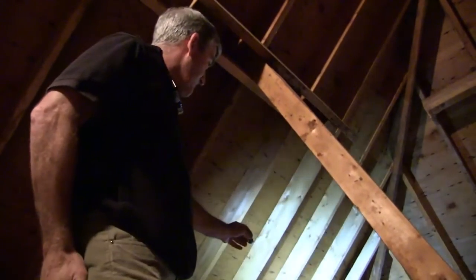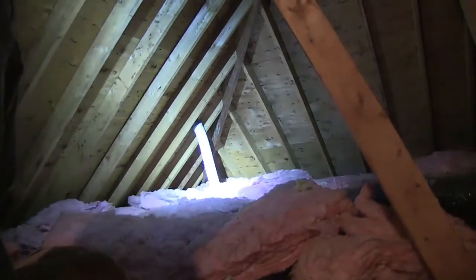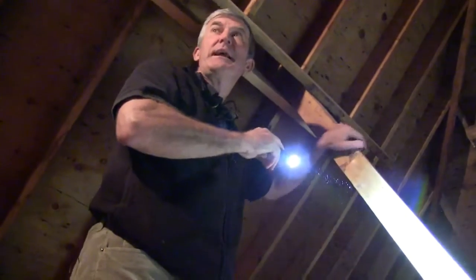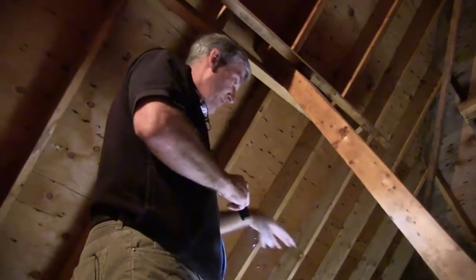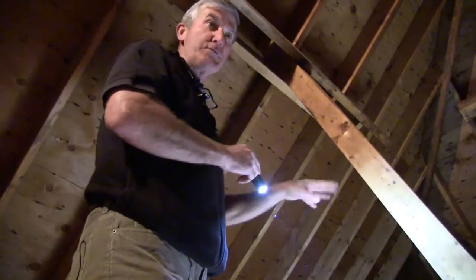Also, looking at the area where one of the bathroom fans comes up into the attic space, that vent fan coming up would also be another critical area for air sealing. And up in this space we also have an air handler for the air conditioning unit, so we've got grates that go into the second floor ceiling that we'd want to look at and make sure are all sealed up.